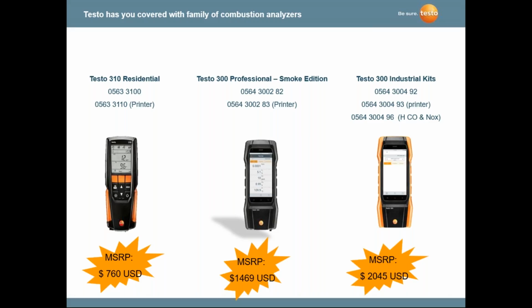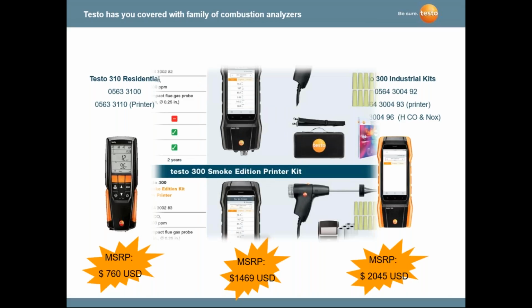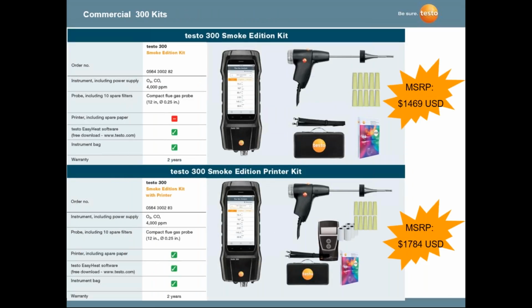We're covering you with a whole family of these instruments. And if you look at the Smoke Edition, this is a new edition that we added this year. It's black, it's not orange. That's why we call it the Smoke Edition. But you can see that it measures oxygen and CO. And as I indicated, all our analyzers have temperature measurement standard and pressure measurement standard. The warranty on the Smoke Edition is 2 years. The Smoke Edition with printer, obviously, you're getting printer and printer paper, so you have a hard copy of your test results. And don't forget, these come with Wi-Fi, so you can transfer the readings very quickly through the internet.